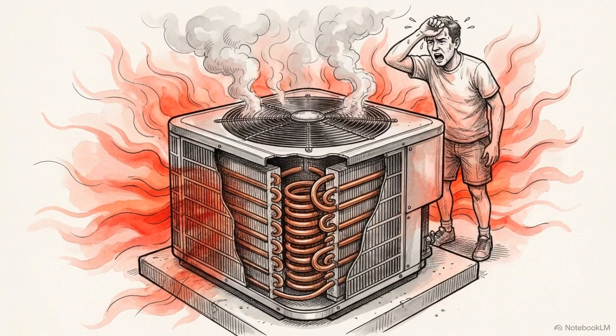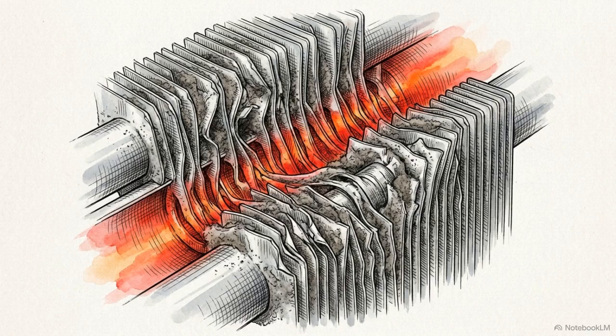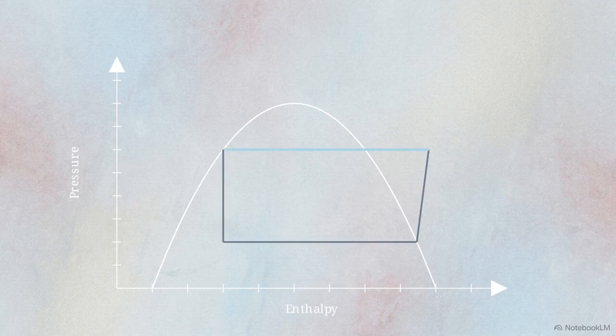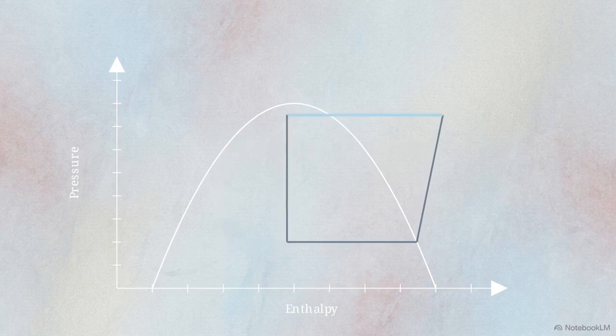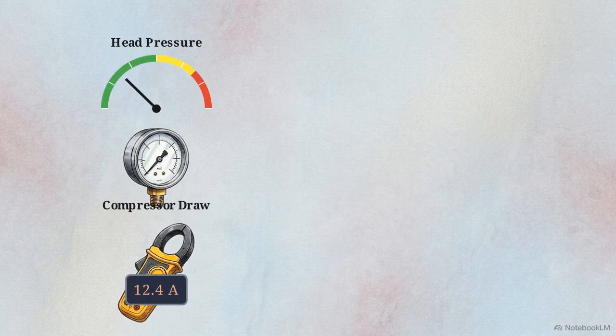When a system goes down, nearly all condenser failures share the exact same root cause: a physical inability to reject heat. In an air-cooled unit, blocked or dirty aluminum fins act as a thermal blanket, aggressively trapping heat against the copper tubes instead of dissipating it. Returning to our pressure enthalpy chart, we can see the domino effect. If the heat remains trapped, the refrigerant cannot fully condense. To compensate, the internal pressure spikes dangerously high, shifting the condenser line violently upward on the y-axis. This high-pressure state correlates to symptoms technicians observe: abnormally high head pressure, excessive electricity draw, and rapid compressor overheating.